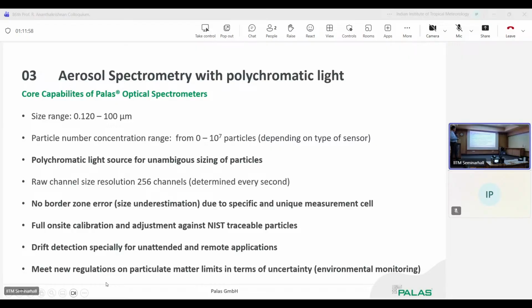Our spectrometers, the size range which we serve is from 120 nanometers up to 100 micrometers, depending on the device and the sensor we use. We can cover particle number concentration ranges from 0 up to 10 to the power of 7 particles, also depending on the type of sensor and instrument. We use for spectrometry typically polychromatic light, so we don't use laser sources. There's a reason behind that, I will tell you later. And we have high resolution sizing with 256 channels over typically 2 decades.